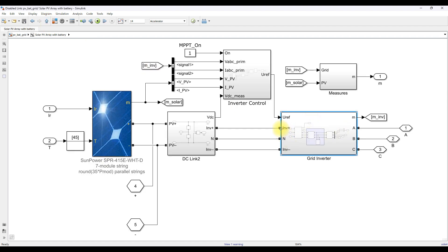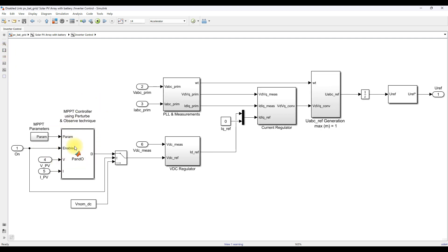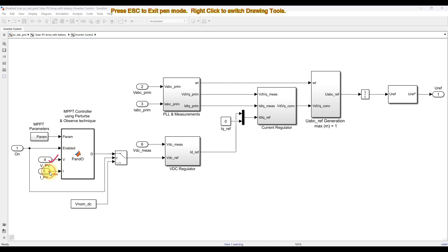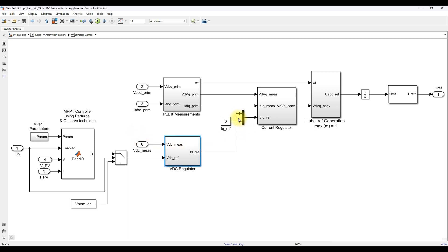The grid inverter is controlled using the P&O MPPT method. MPPT generates a reference voltage based on the PV voltage and current. This reference voltage is compared with the DC link voltage, converted to per unit by dividing by the nominal DC voltage, then processed via a PI controller to generate the id reference. The id reference serves as the reference current for real power injection at the point of common coupling, while iq reference is set to zero since only real power is injected.